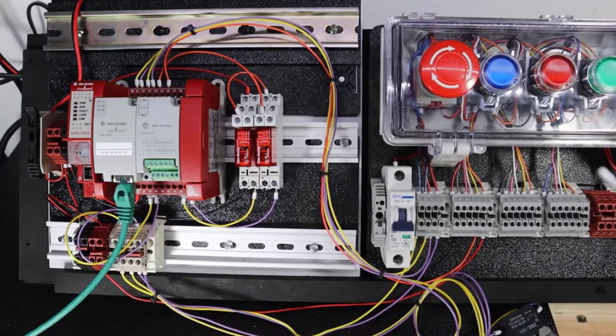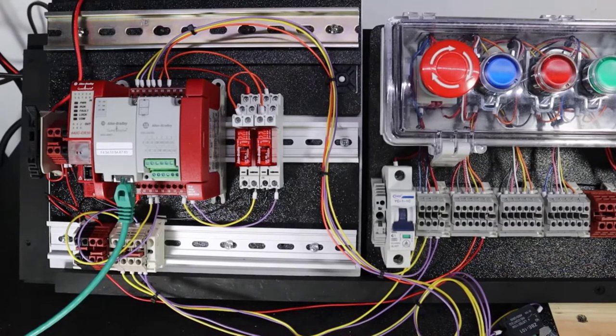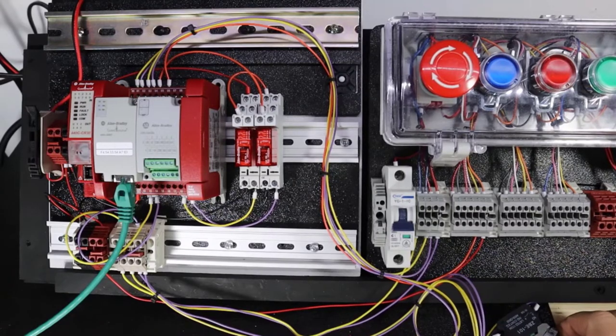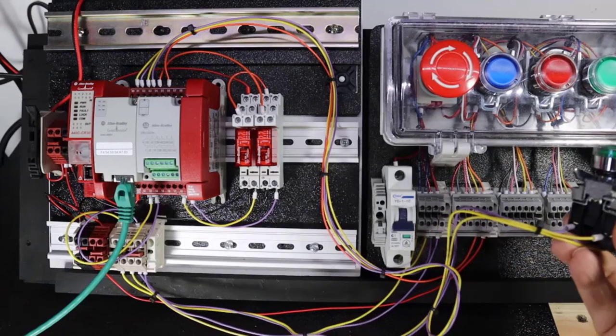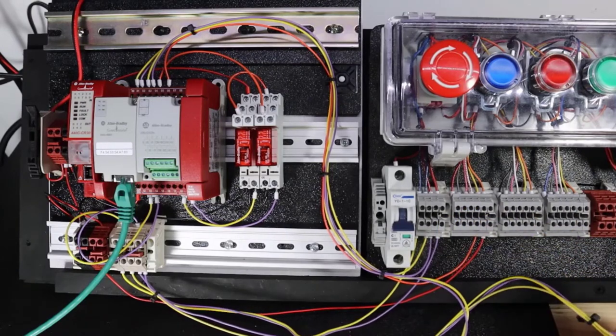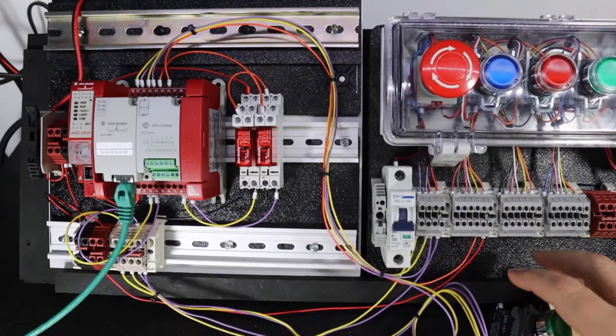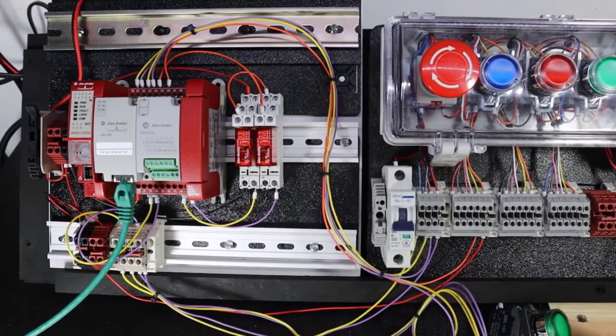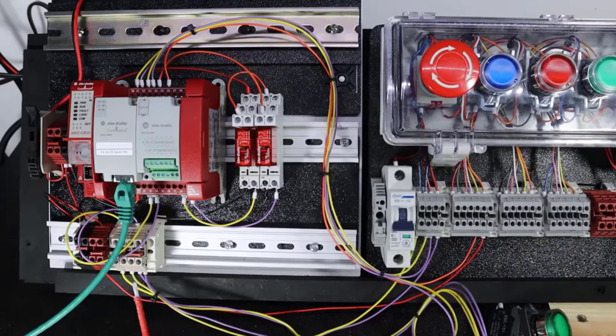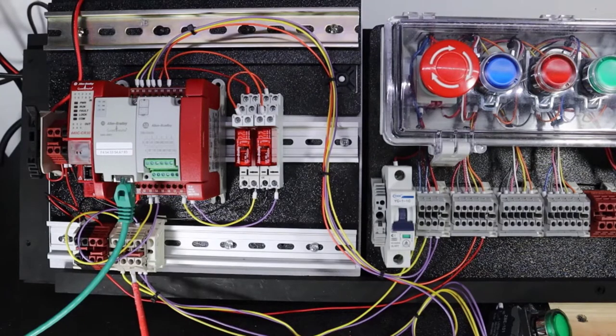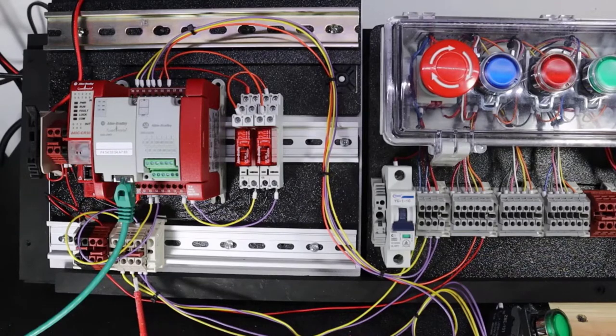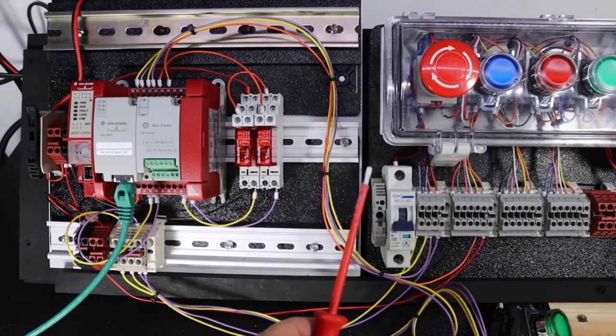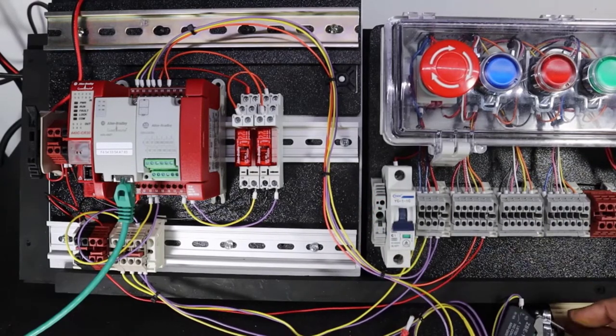This is our new hardware configuration. We haven't really added that much, but just to review what we do have. This is our handheld enabling switch, and this is the e-stop that we're using. It's a twist to release, and we came off of 12 and 13, which are the pulse test outputs, on a yellow one purple, to the e-stop and also to our enabling switch.